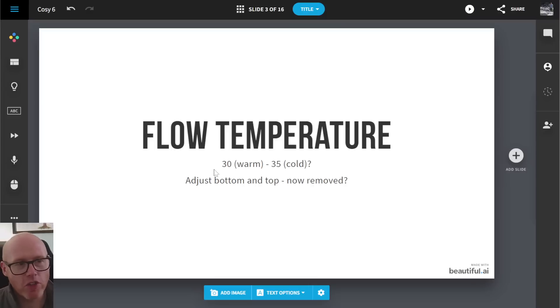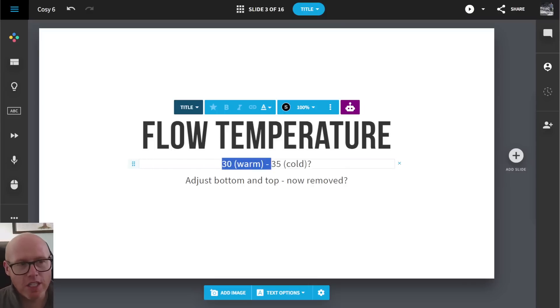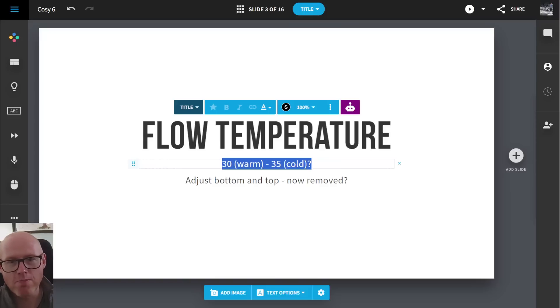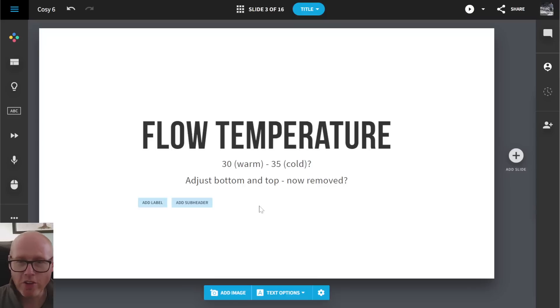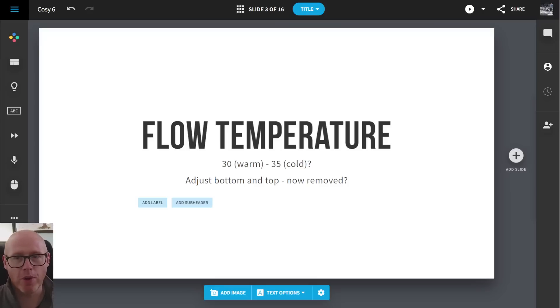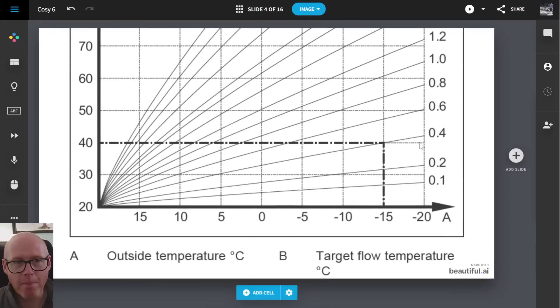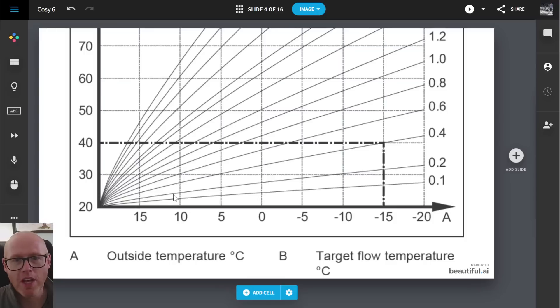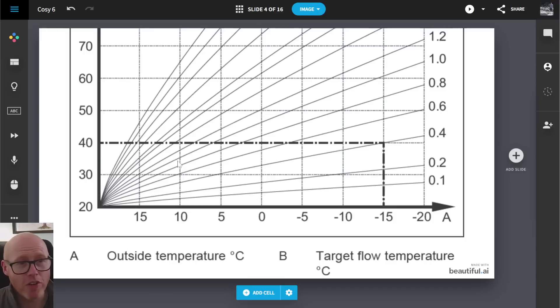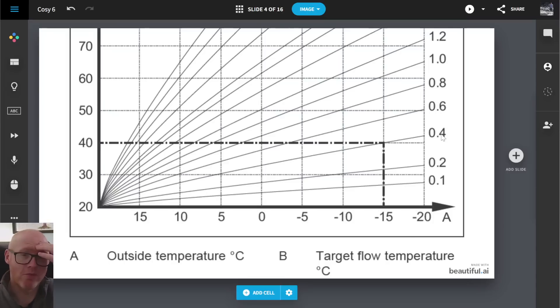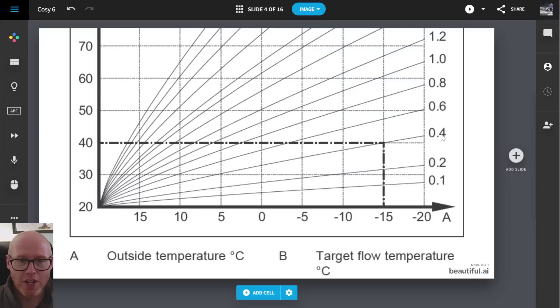So the interesting thing that he alluded to there that we learned about the Cozy 6 was that he was able to change two flow temperatures. So he was able to manually input the weather compensation curve that he wanted. I know some manufacturers do that. They can allow you to adjust the bottom point and a top point and sometimes a middle point. Vaillant that I'm familiar with, they don't. They just, you're allowed to pick one number and then Vaillant says this is the curve that the heat pump will operate on. And so he chose a curve that he said 35 degrees when it was cold. So if we look at that, he's roughly looking at somewhere like a 0.4 heat curve, which in Vaillant terms would be really just underfloor heating only unless you've got massive radiators or a really well insulated house or something.